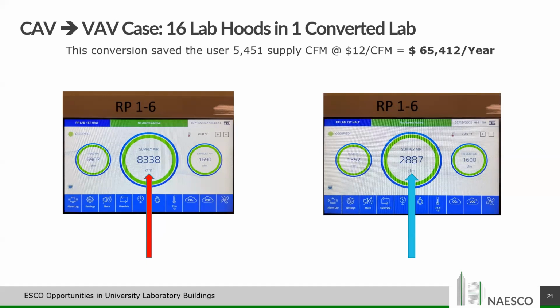necessary to feed the existing hoods was about 8,300 CFM. Once we turned on our VAV system and started getting that reduction, we were able to bring that down to 2,800 CFM. So you can see a savings of about 5,400 CFM coming from the supply. In this particular case, in the Northeast Boston area, saving the customer about $65,000 a year in air.